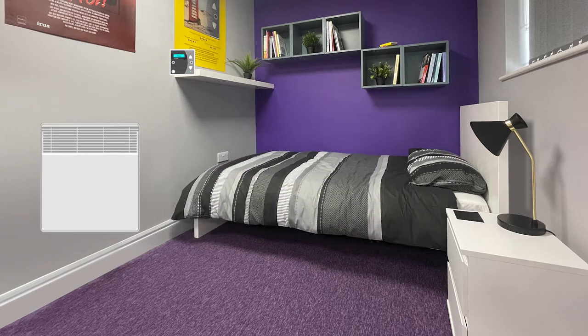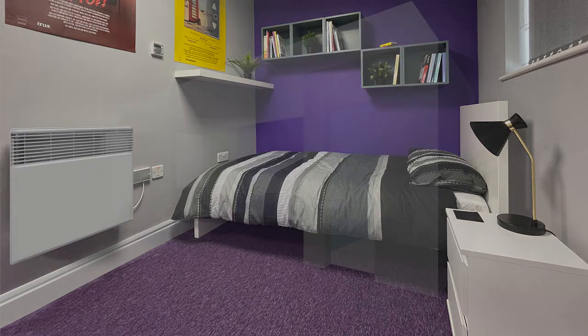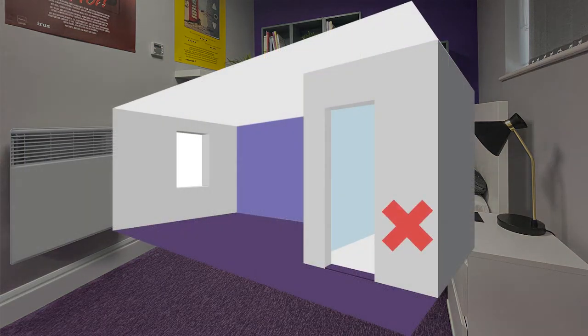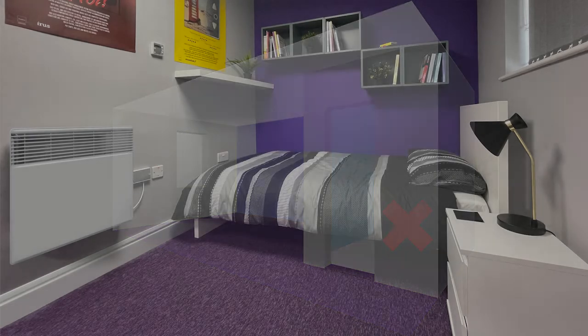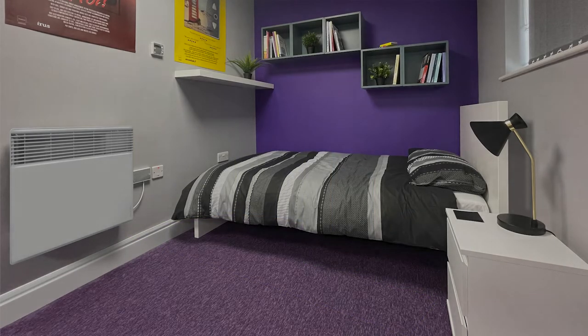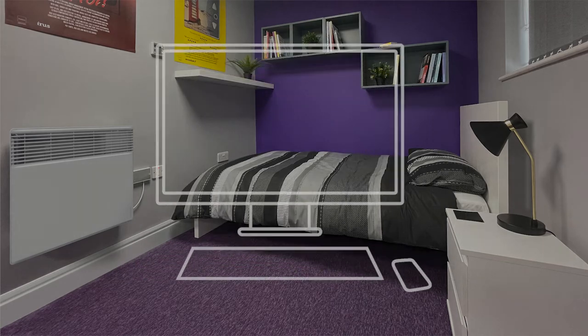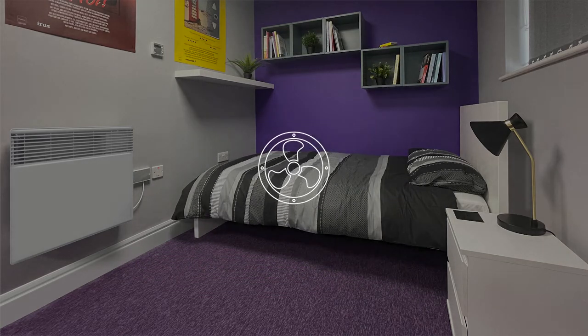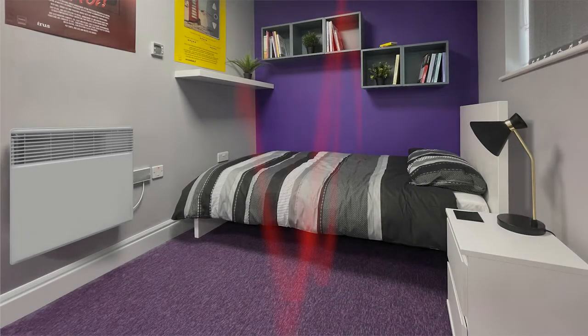Position the control unit centrally in the main body of the room, avoiding narrow entrance lobbies. Appliances that generate heat should not be in proximity of the controller, for example, televisions, desktop computers, fridges, or ventilation systems. Position the control away from any non-ambient airflow, hot or cold.